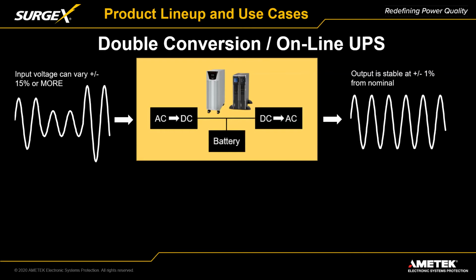So if it ever happens to go to battery mode, there is no switching. In standby and line interactive UPSs, there's a relay inside that switches between the incoming line voltage and, if that line voltage goes away, switches over to the inverter to get the backup. In those kinds of systems, you're going to get 4 to 10 milliseconds of dropout time right before the backup power comes on.